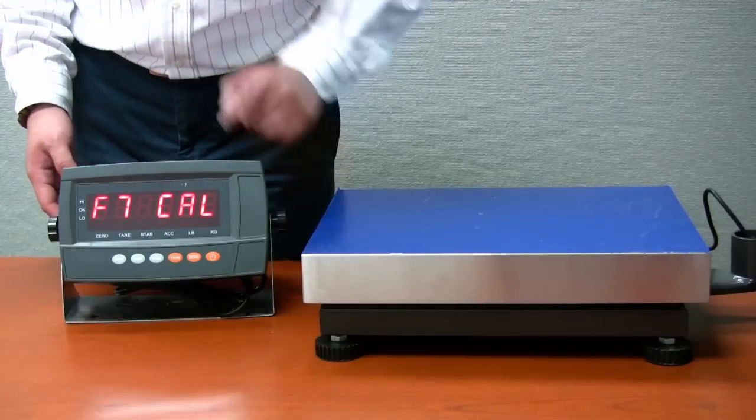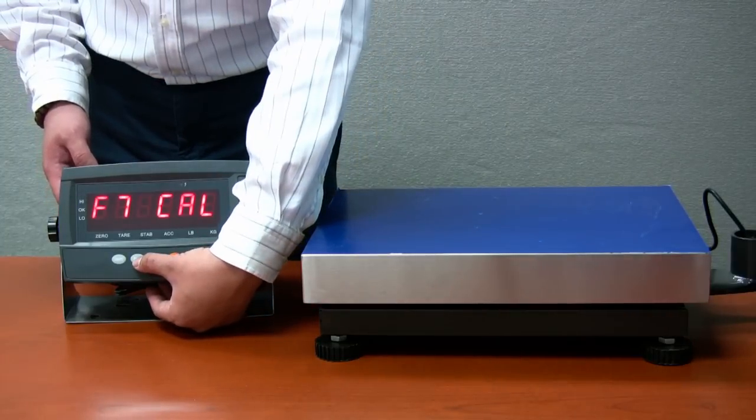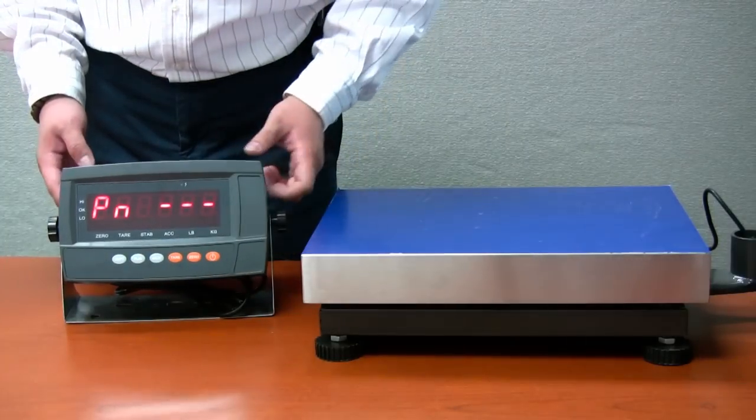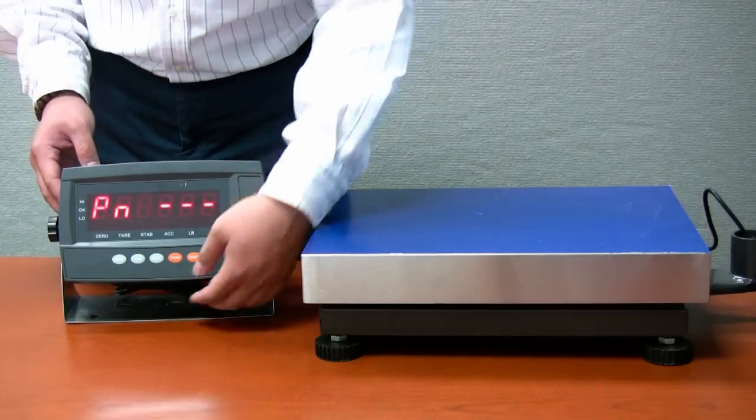Press TAR key six times and the indicator will show F7 C-A-L. Press function key to enter calibration password. The initial password is four zeros.